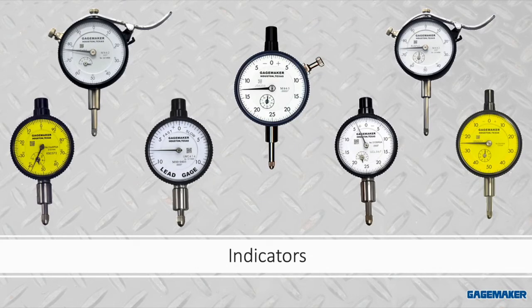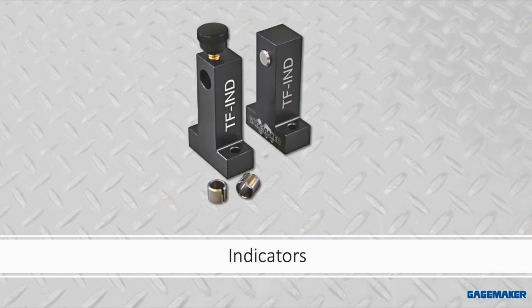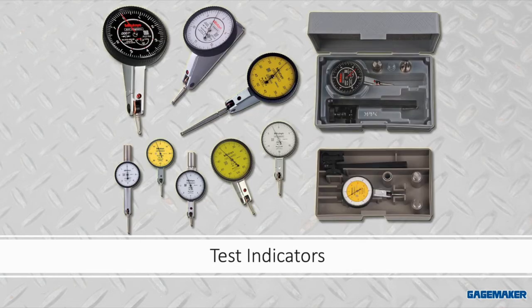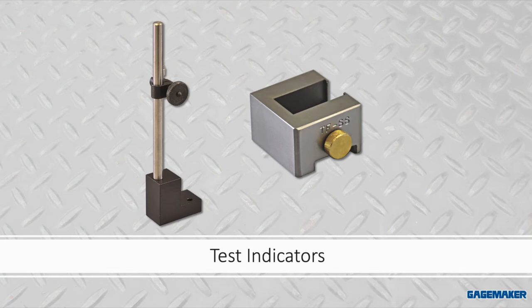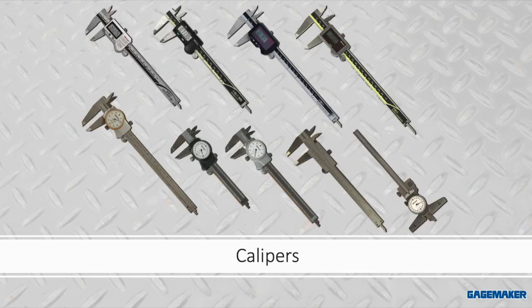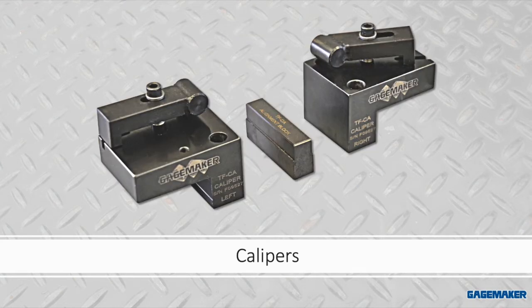Dial indicators. A TFIND is basically a vertical post with a hole and set screw to secure during the measurement process. Test indicators. Basically a combination of a TFTI support stand and TFSS fixture, which is a specialized version of a precision anvil, a support stand, and hook to traverse the probe during calibration. Calipers. The TFCA fixtures are a combination of two clamps to secure the jaws, align them to the axis of the measuring scale, and a support arm to hold the instrument during calibration.